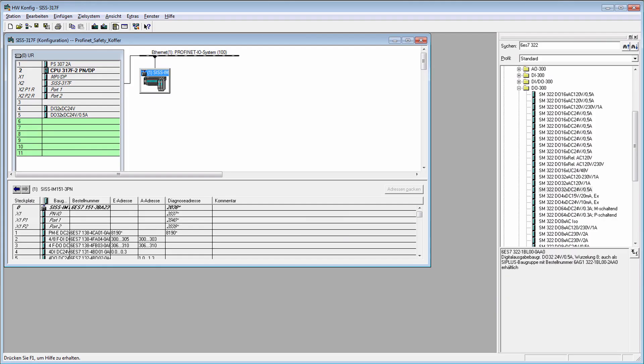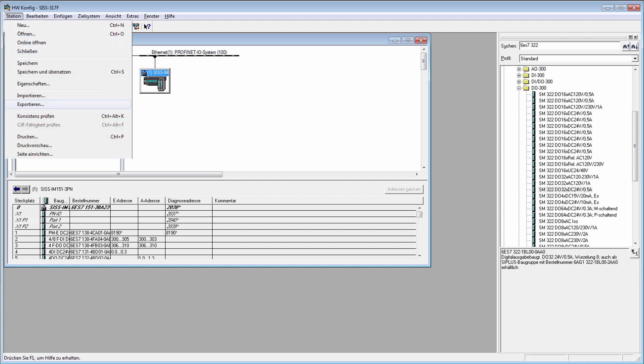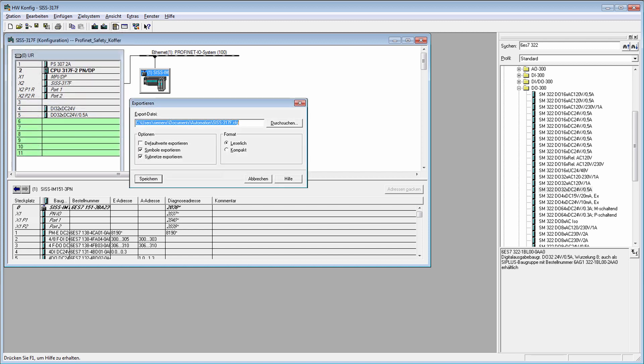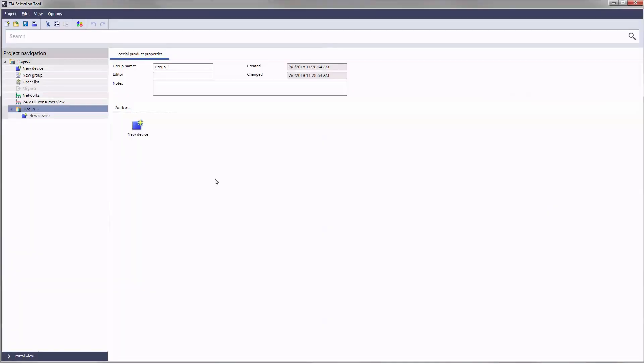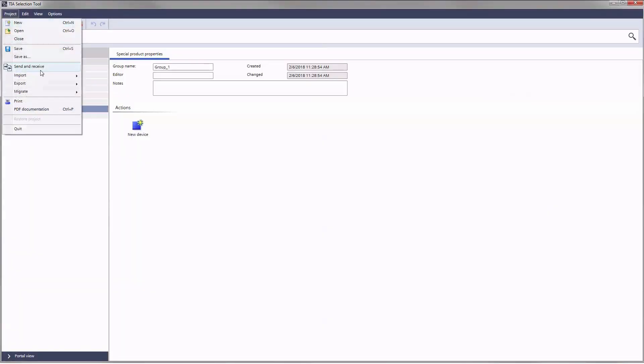You can also start a migration from HWCONFIG. First export your configuration with the central module and all connected distributed IOs as a CFG file. Then open it in the TIA selection tool.